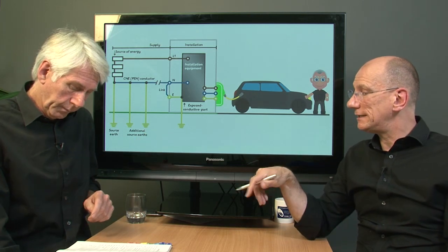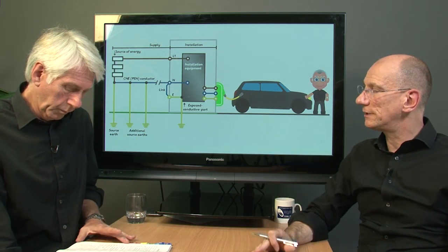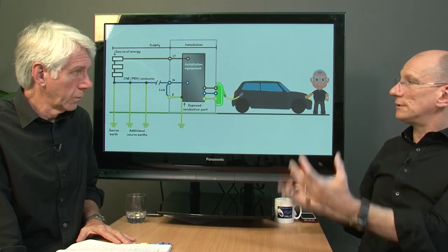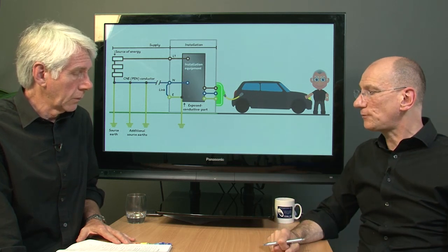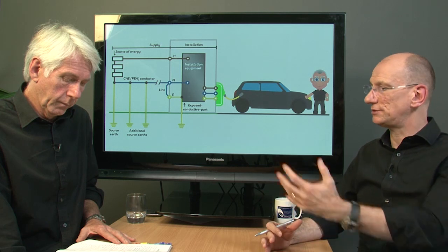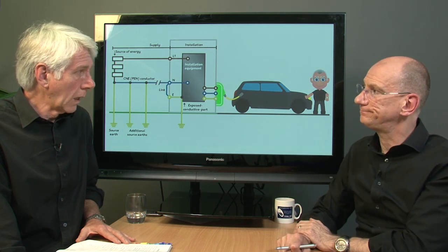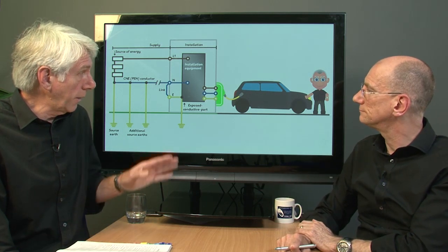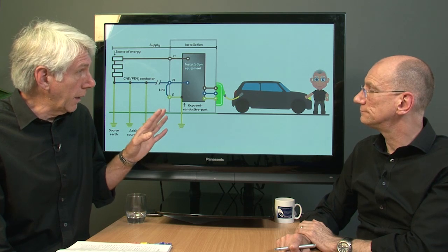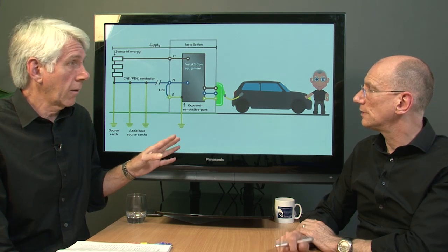That requirement does go on to specify that you need to make sure that in the event of a fault, you still don't go above 70 volts. So you need to do some serious maths, which are given in the annex. But we are in a serious situation in that if there is a problem, the RCD in the house won't necessarily pick it up, will it?